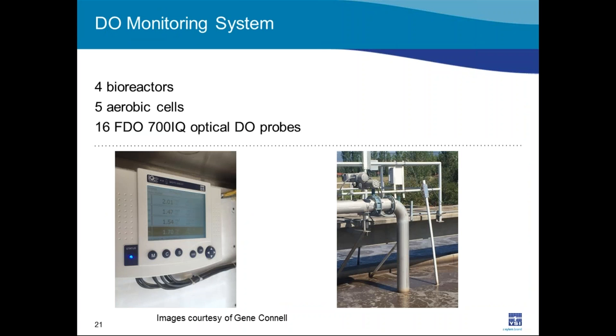The DO monitoring system consists of 16 optical DO probes installed in four bioreactors, each having five aerobic cells. A picture shows one DO probe installed at the end of a PVC pipe in the aeration basin, with the air drop leg and air control valve also visible — an important feature of the system configuration.